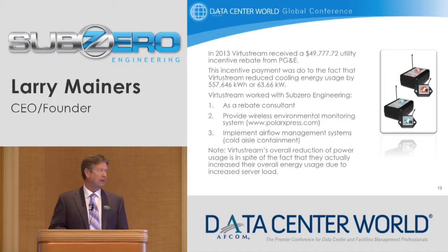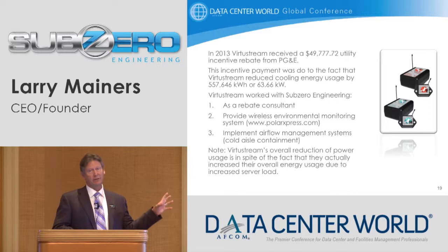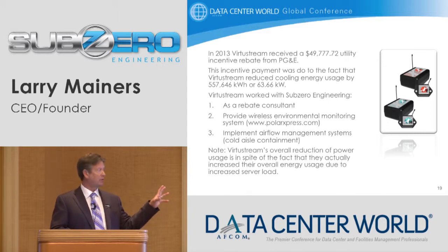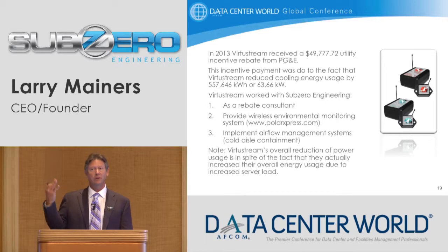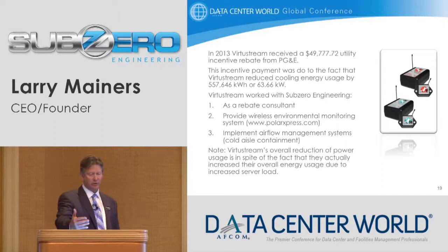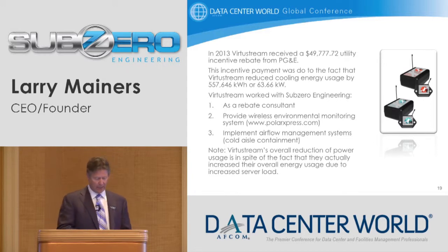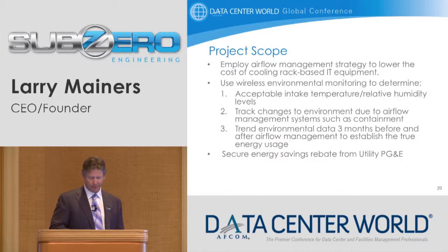There are other, more robust systems that are really pretty awesome. They're somewhat expensive, but they can actually do this on the fly, changing the temperature and relative humidity set points literally based on what they're reading at the IT intake and volume. So whether it's a wireless inexpensive system or a terribly robust system you're planning to use in the future, either way you've got to have a way to monitor this before you can make those changes.